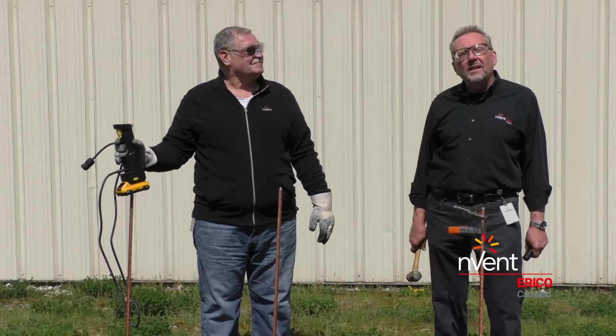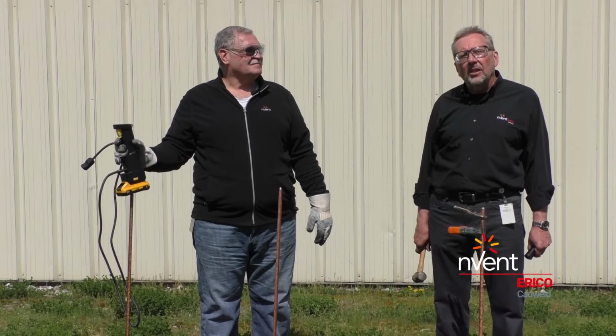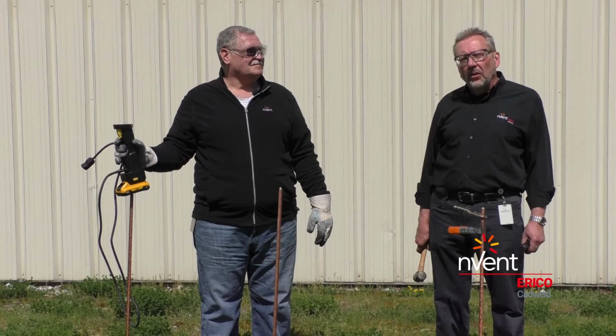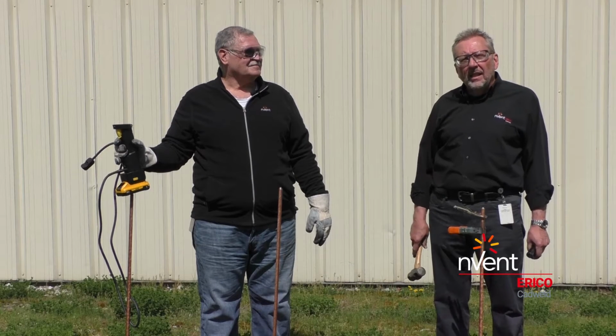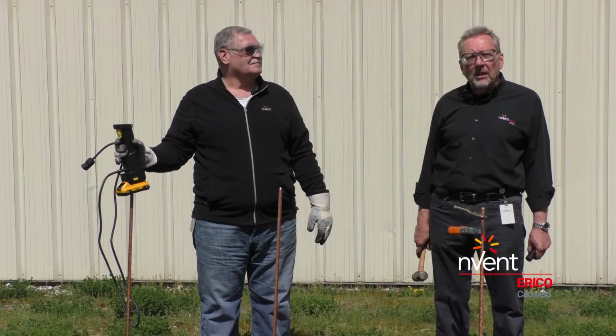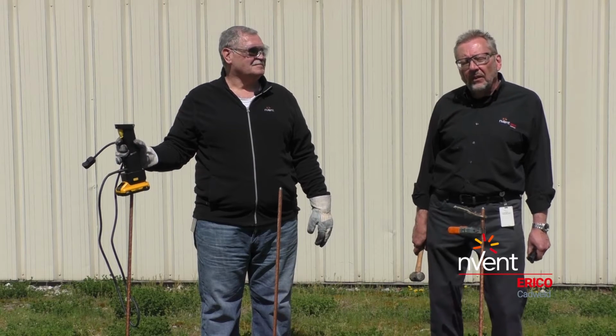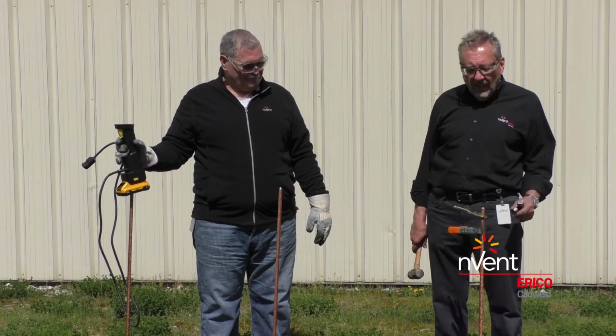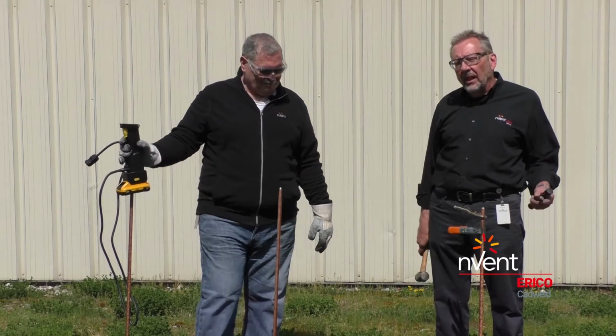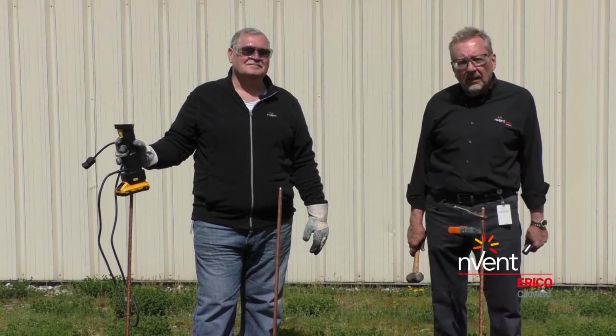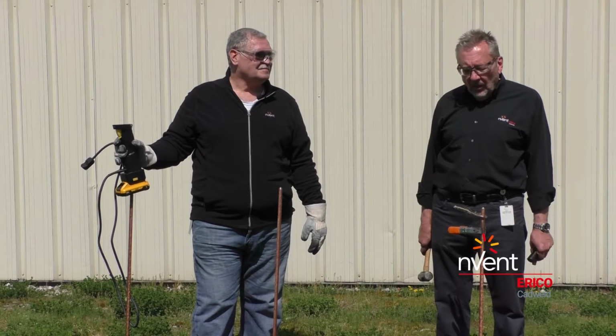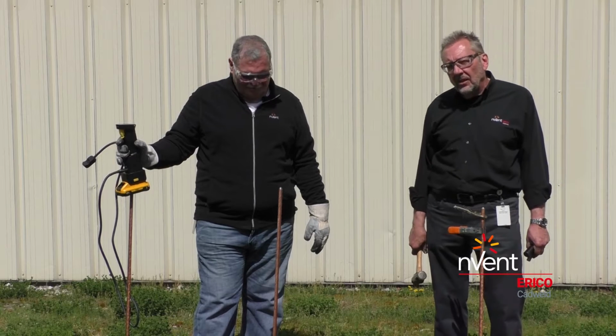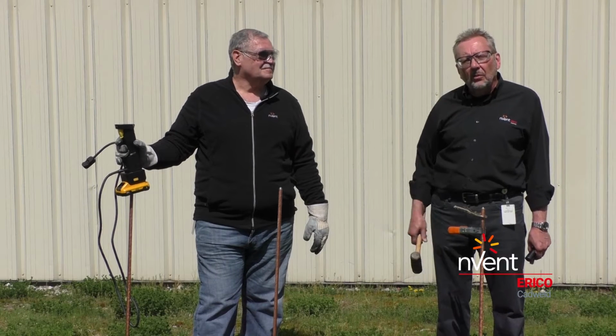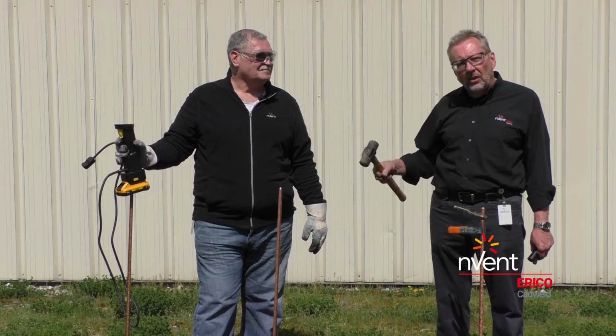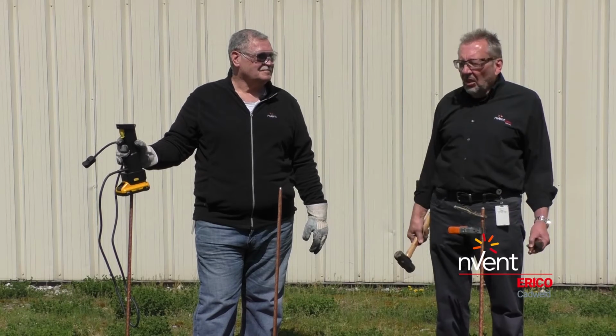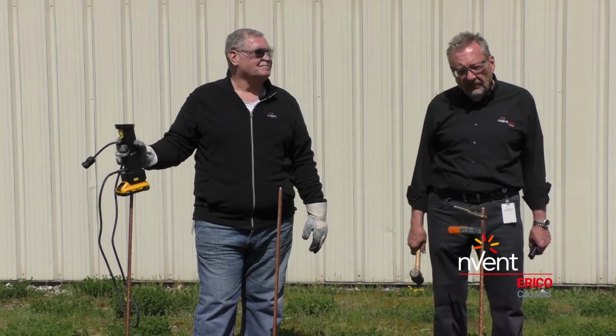Now we're moving on to the next phase of training, where we start making connections. Our focus will be on the main types of Cadwelds used to build a grounding grid. At the start of any grounding grid, ground rods are driven into the ground and joined with cables to make a ground ring. We've driven 3 ground rods into the soil today so we can do a GR, a GT, and a GY connection—three of the main connections for cable to ground rod.